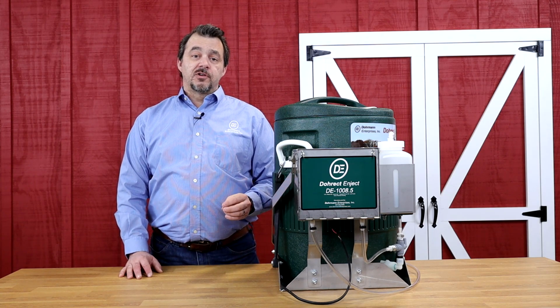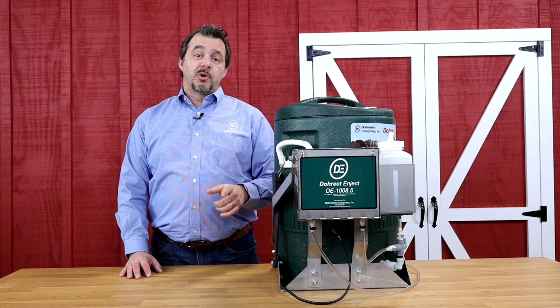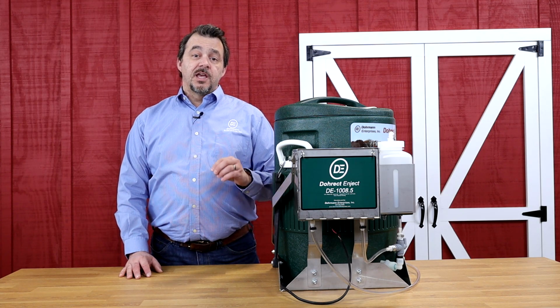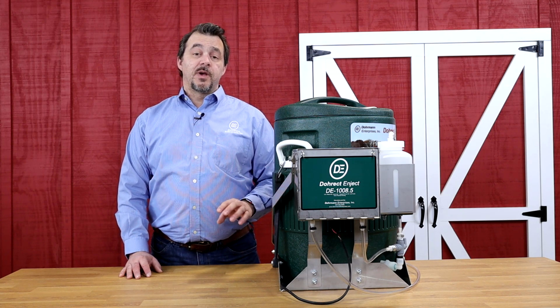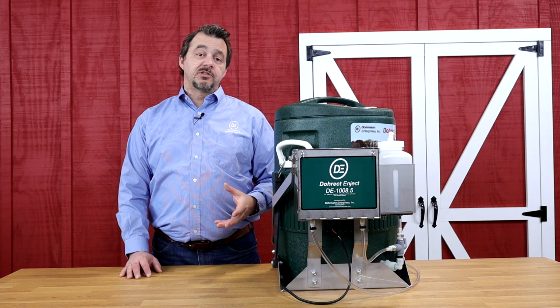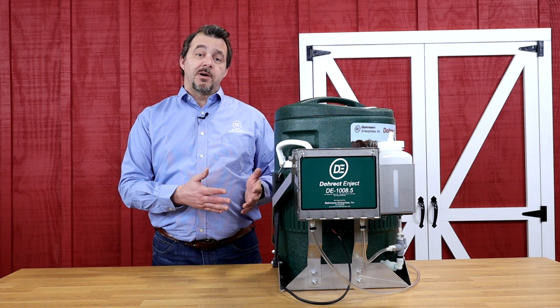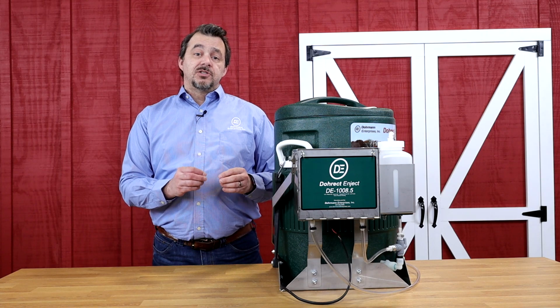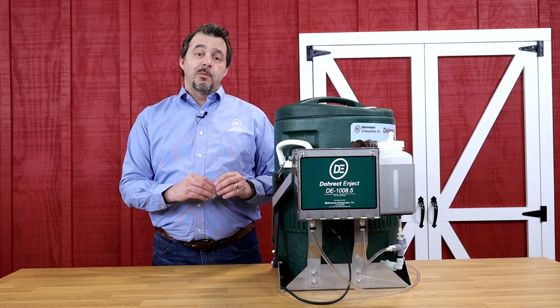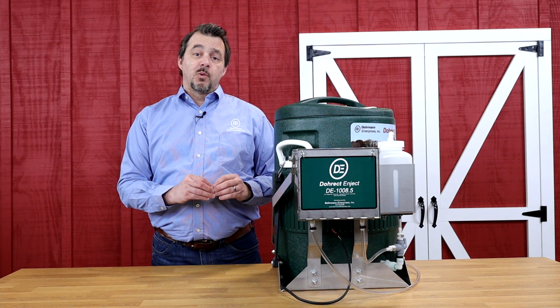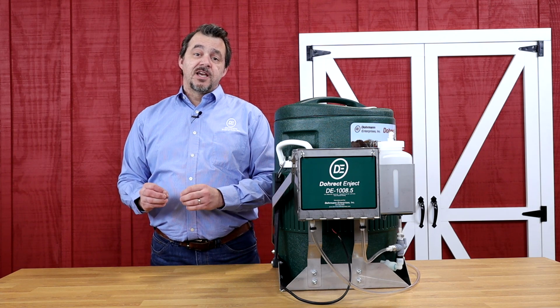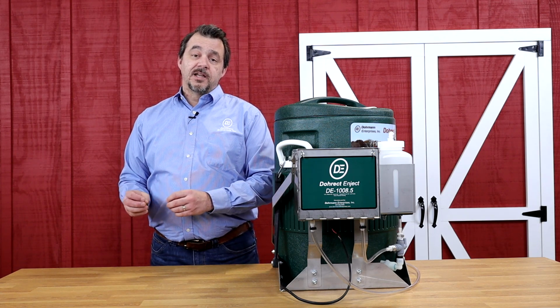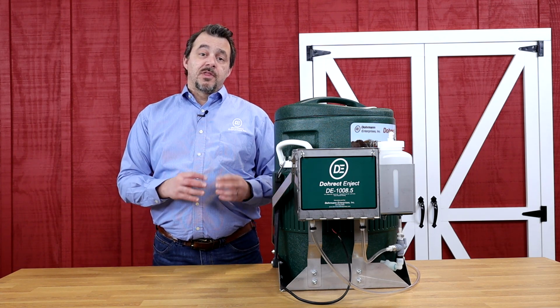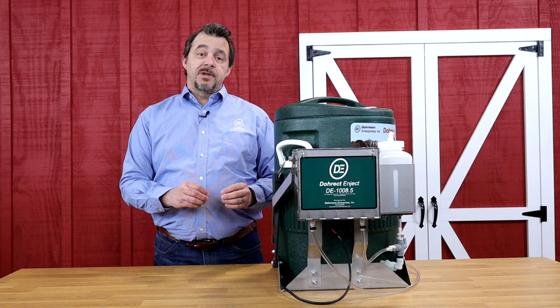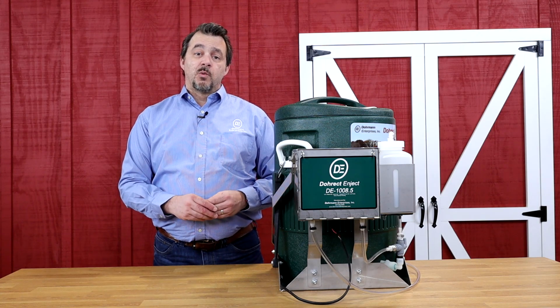And with that, our first question will be, does your motor run? If your answer to that is no, we have to make sure that we address that first before we can look at why the pump may not be pumping. So in the video description below, we will place a timestamp for where we start troubleshooting the motor not running.